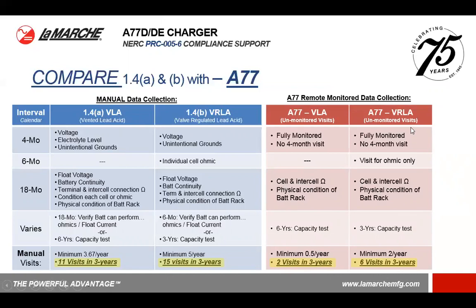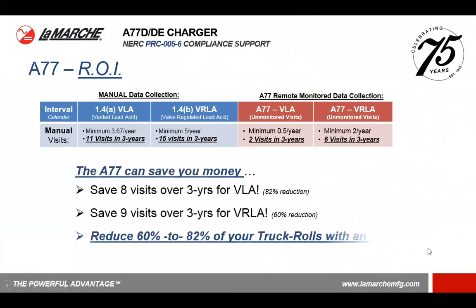Whereas with the valve-regulated lead-acid, the 4-month interval is also fully monitored, but you have to return for ohmics only. This results in ultimately 6 visits in 3 years. So let's look at the return on investment, manually collected data versus the A77. Really, the A77 can save you 8 visits over 3 years. For vented lead-acid, that's an 82% reduction. Or it can save you 9 visits over 3 years with valve-regulated lead-acid, and that's a 60% reduction in your total visits.